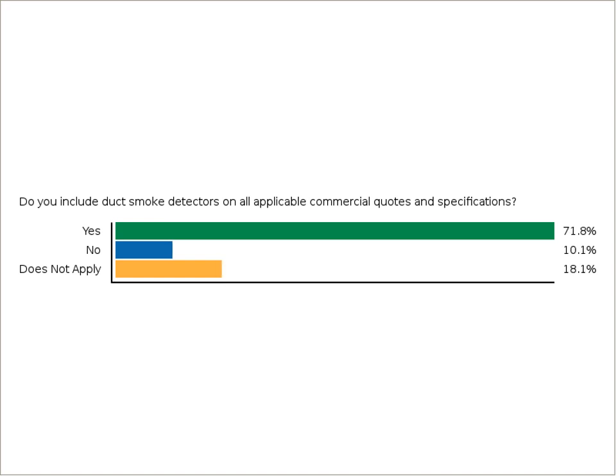Very good. And they're asking a question about addressable duct detectors. Do we offer addressable duct detectors, or how can they get a duct detector to be addressable? System Sensor still manufactures addressable duct detectors for our fire alarm panel partners. Those addressable intelligent duct detectors need to be purchased through the fire alarm panel manufacturer. An additional way to do that is if you're in an application where you need an addressable duct detector, you can always add a monitor module to a conventional duct detector, allowing it to interface with an addressable fire system.